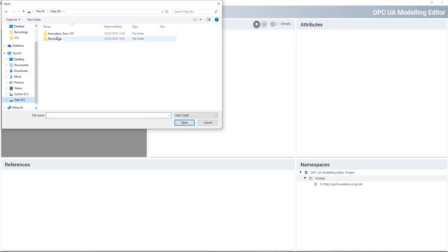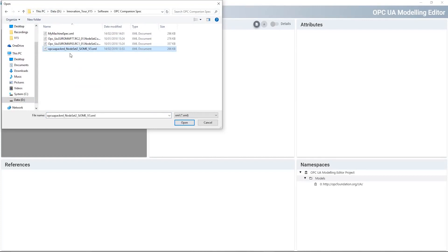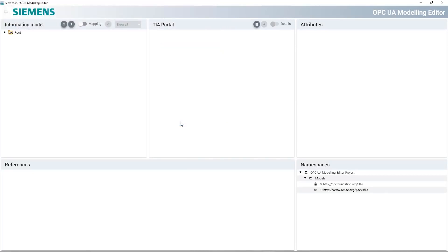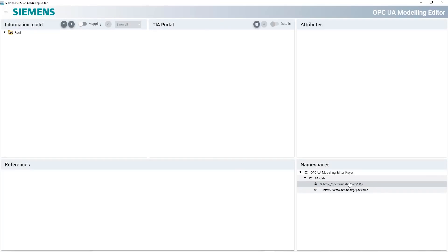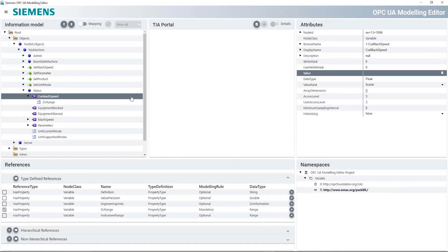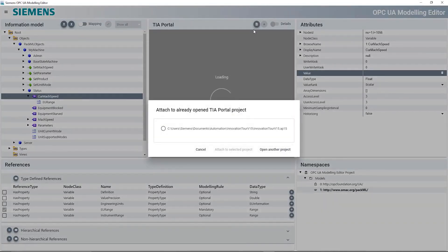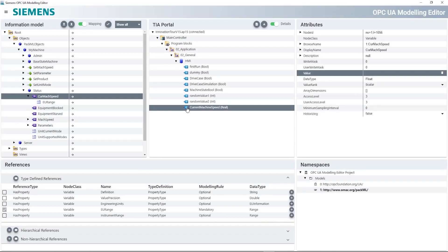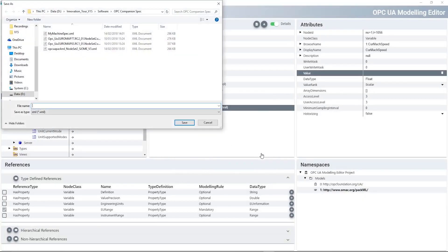Once we've opened the tool, we can import the Companion Specification as the foundation, which we've already downloaded from the website of the OMAC Foundation. This specification contains all the data types and structures required by the specification and makes life considerably easier for us as a result. Once the data interface has been modeled, the structure still needs to be linked to the data from the S7-1500. SIOME provides direct access to TIA Portal data for this. After browsing through the data, it can easily be linked to the structure of the Companion Specification by dragging and dropping it. When the interface is fully modeled, an XML file is exported, which is then integrated into the S7-1500 as the OPC UA server interface.